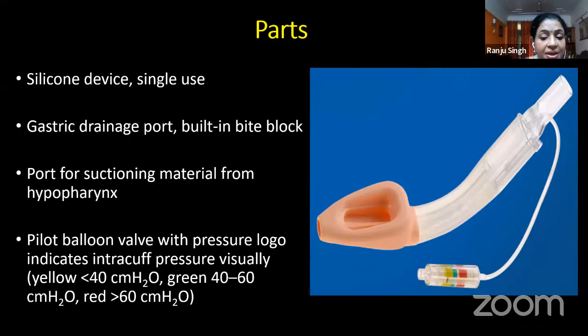What is specific about this device is that it has a pilot balloon valve with a pressure logo. So pressure monitoring can take place with the help of this pilot balloon valve. Although pressure monitoring of intracuff pressure is recommended for all devices, you must have a monitor to monitor the intracuff pressures. But in this device, this pilot balloon valve with the pressure logo can be used to monitor the device visually. Once you inflate the device, it will tell you whether it is overinflated, appropriate, or underinflated.